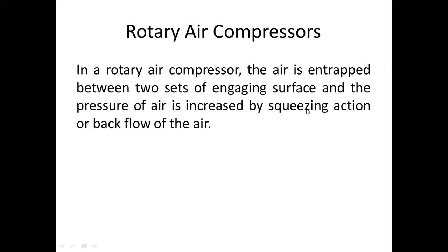As we know, in the reciprocating air compressor, the maximum delivery pressure may be 1000 bar. Here in a rotary air compressor, the maximum delivery pressure is 10 bar only. In the rotary air compressor, the air is entrapped between two sets of engaging surface and the pressure of air is increased by squeezing action or backflow of the air.